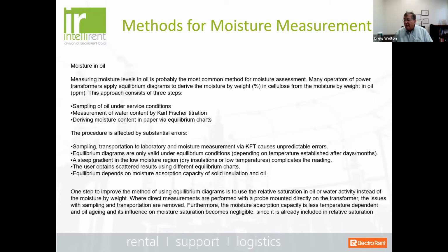Measuring moisture levels in oil is absolutely the most common. And of course, you can sample the oil under service conditions, and then we do a dew point, or a measurement of water content through a Karl Fischer titration, and that's done usually under laboratory conditions. And that is deriving, or trying to estimate, the content of moisture in the oil, trying to determine what it is in the paper insulation using what they call equilibrium curves. And this was established by IEEE many years ago.